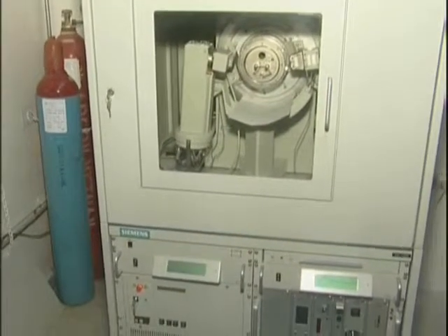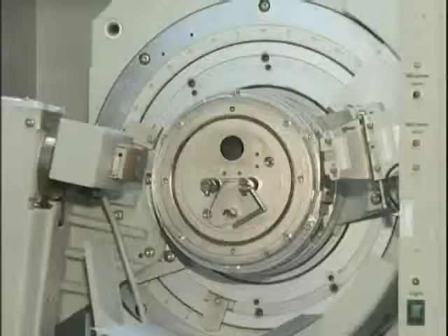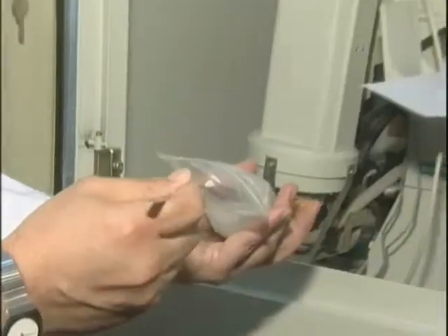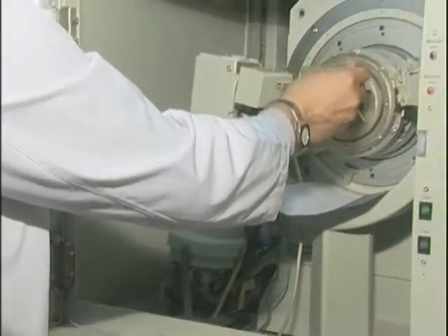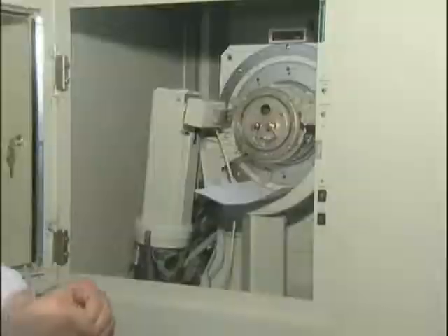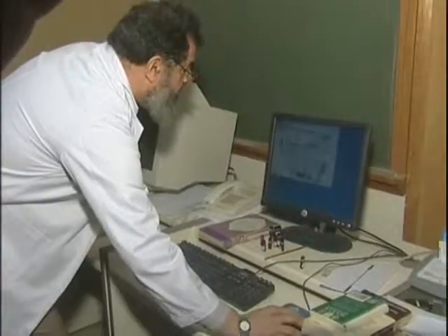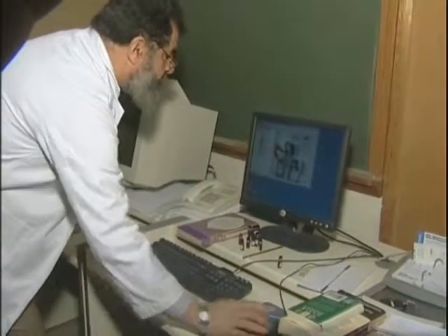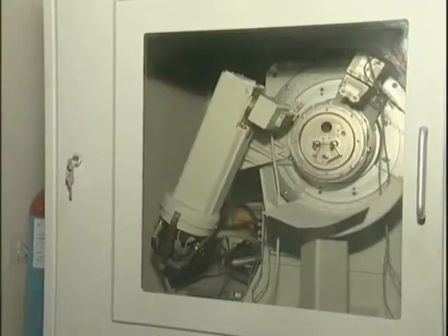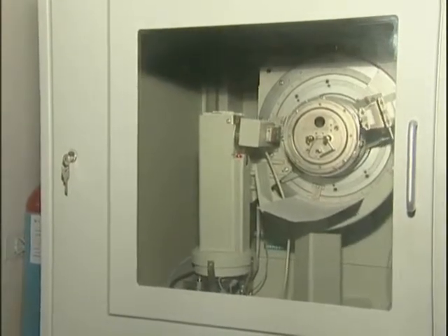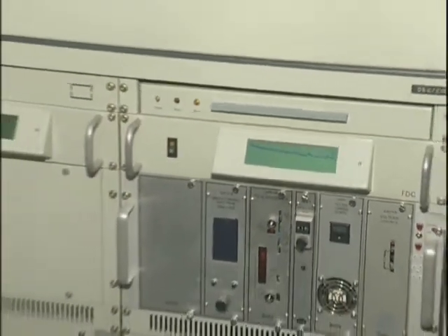The D5000 powder X-ray diffractometer from Bruker relies on Bragg's equation. It uses copper radiation from a rotating anode X-ray generator cooled by running water. The X-ray generator and detector are mounted on a goniometer. The fine movement of the goniometer produces the X-ray diffraction pattern.